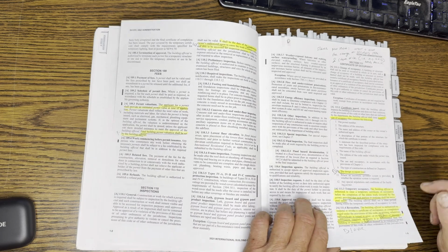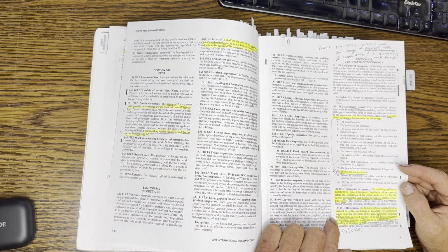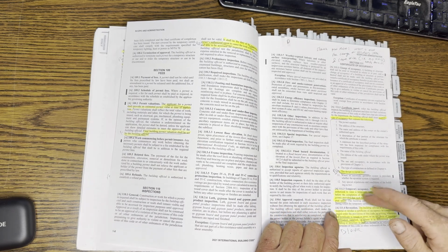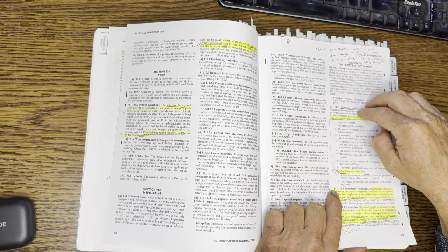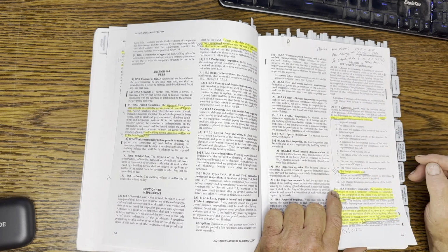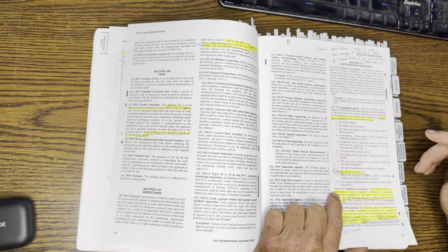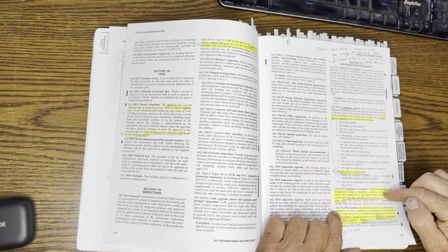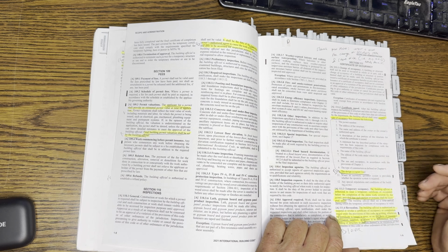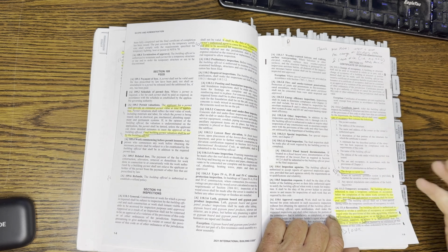yeah, so you can have a temporary occupancy permit, TCO, but you have to itemize. So sometimes you have a building, you can't do a certificate of occupancy because there's things that are missing, like let's say suppression's missing or an alarm system's missing. But you're allowed to take occupancy in certain situations as long as you have compensatory actions associated with it. Like in the case of an absence of suppression, minimize combustibles, fire patrols, that kind of thing.